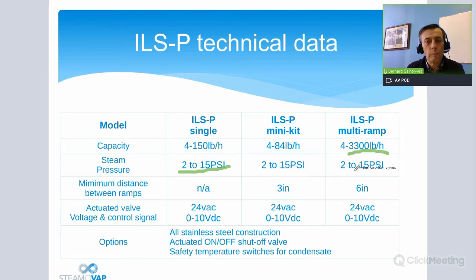Why this? It's just to stay under the maximum pressure to have a certified welding component made. So we can go higher, but then you will increase the price a lot, because we need all the certification for welding and the pressure vessel. This is why any manufacturer will limit at 15 psi.